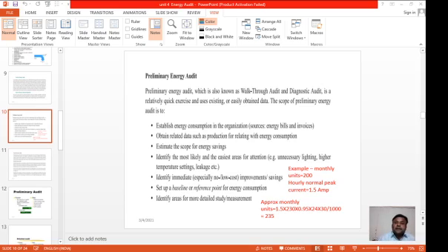Then you should have a walk in the electrical installation or switchyard and see whether the earthing is done properly, and earthing pits are being properly watered, and so on. Then you can see what are different types of lights in the yard, in the building, in the passage, in the garden, and check whether they are working or not.